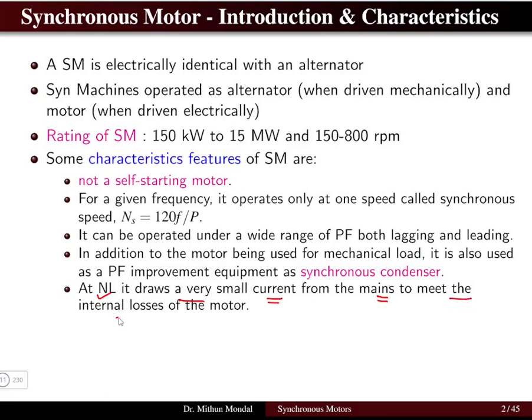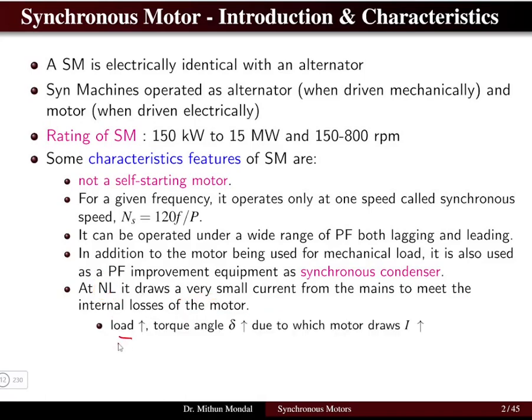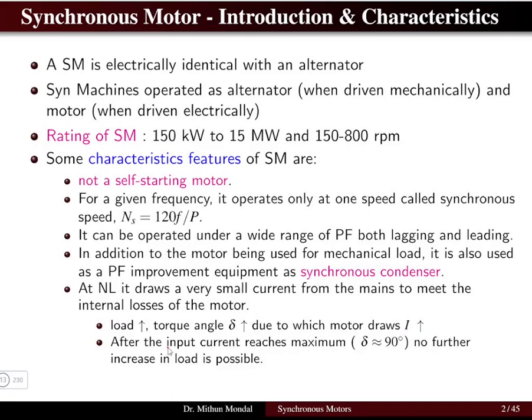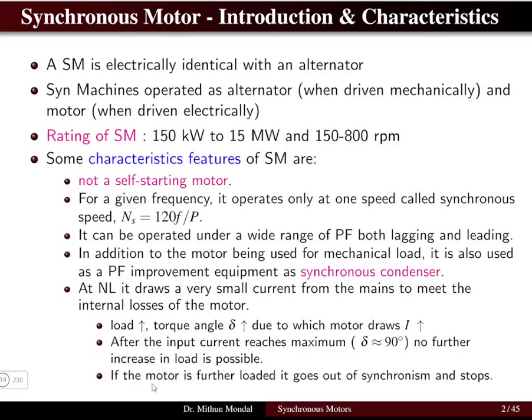At no load, the synchronous motor draws a very small current from the mains to meet the internal losses of the motor. When the load increases, the torque angle increases, due to which the motor draws more current. The increase in load is tracked by the motor with an increase in load angle. After the input current reaches the maximum — which occurs when the torque angle delta reaches 90 degrees — no further increase in load is possible.